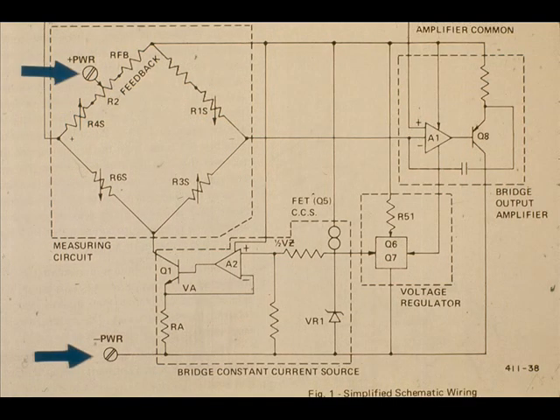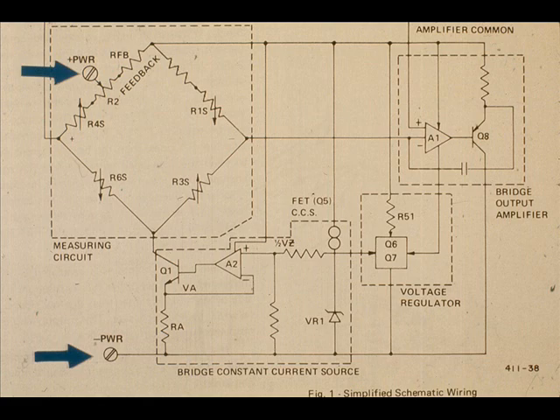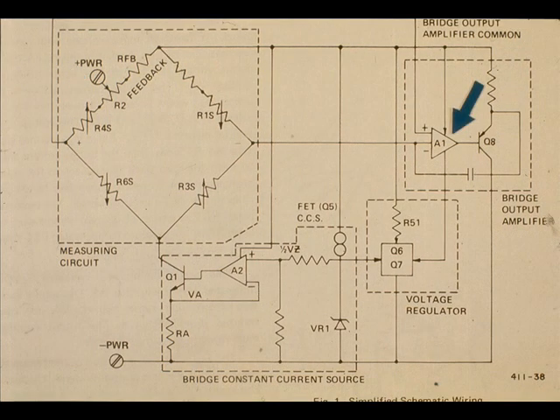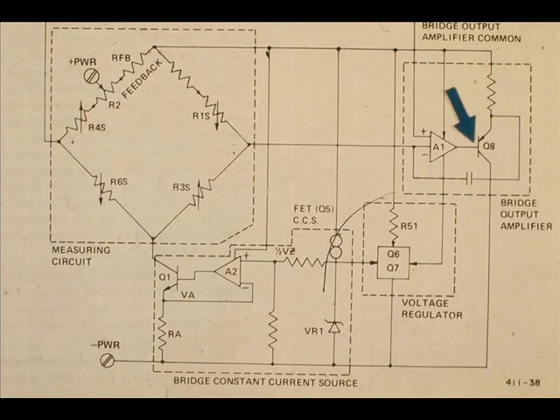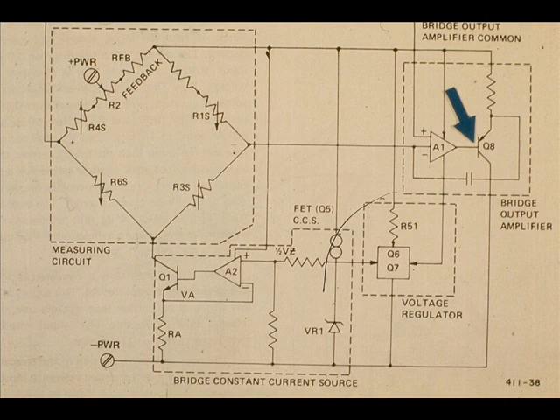24 volts DC is applied across the power positive and the power negative terminals. The bridge unbalance is fed as a negative input to the bridge output amplifier, A-1. This causes the output of A-1 to drive the base of transistor Q-8 in a more negative direction, causing it to conduct more current.